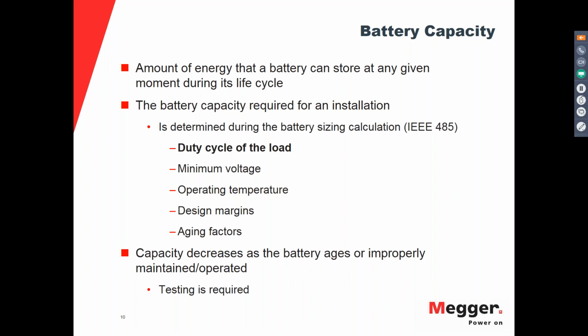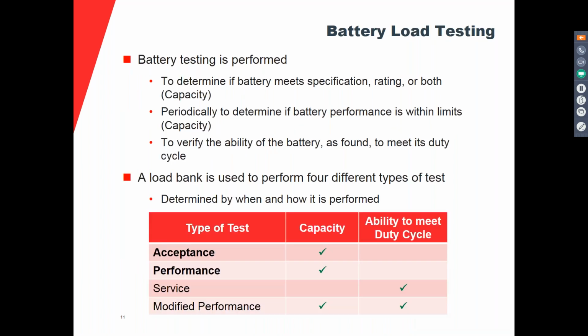As the battery ages, the capacity decreases, and this is where testing is required. We need to check if the battery is holding its capacity or if it's deteriorating, or if the maintenance practices that we are performing are effective or not. The main test you can perform on a battery to determine that capacity is running a load test. And there are three reasons that you would perform the test.